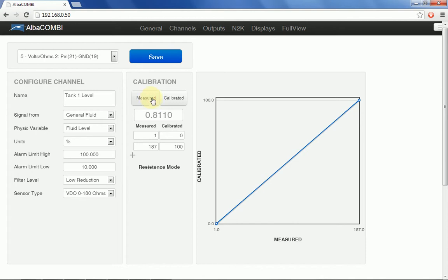Then I press calibrated, which means tell me what data I'm getting after calibration. I press calibrated, and it's 0, which is what I expected since the sender is in its lowest position. When I move the sender to its up position, I measure the signal coming from the sender at around 186-187, and I press calibrated, and I get 100%, which is what I expected.